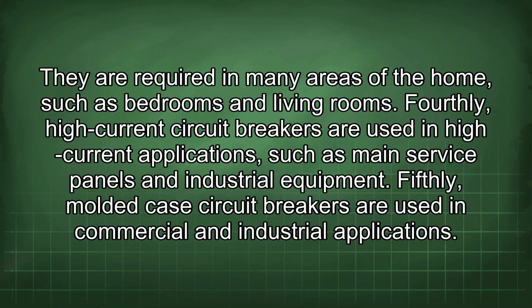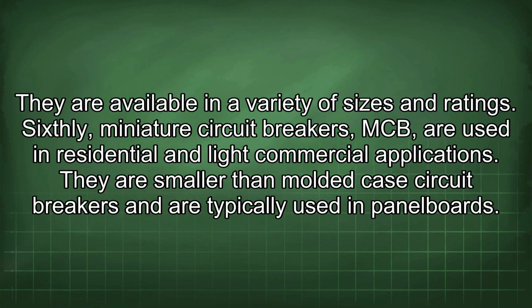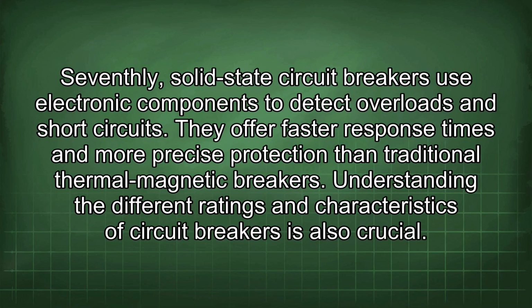Fifthly, molded case circuit breakers are used in commercial and industrial applications. They are available in a variety of sizes and ratings. Sixthly, miniature circuit breakers, MCB, are used in residential and light commercial applications. They are smaller than molded case circuit breakers and are typically used in panel boards. Seventhly, solid-state circuit breakers use electronic components to detect overloads and short circuits. They offer faster response times and more precise protection than traditional thermal-magnetic breakers.